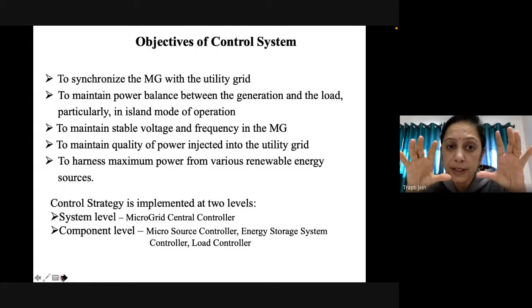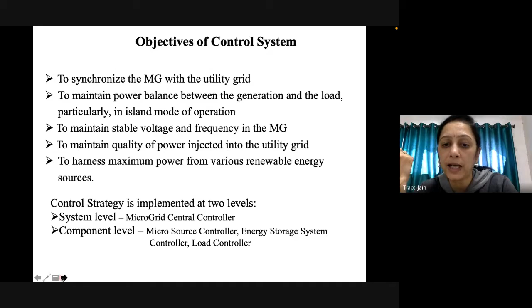This control strategy is implemented at two levels. One is at system level, which is like the microgrid central controller - almost similar to what we've seen as master controller. The other is at component level, where microsources will have a different controller, energy storage systems will have a different controller, and loads will have a different controller.